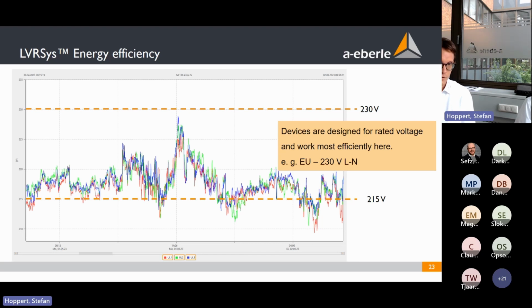For example, all inverter-driven machines are working the best with 230 volts or even a bit higher. Some people in the field say you can save energy if you reduce the voltage. This can happen for some devices. For other devices, it doesn't work or it makes it worse. So we don't want to sell you the system as an energy saving system, but out of our experience, it makes more sense to have it on the nominal voltage, because then all the devices work properly and more efficiently than if the voltage is too low or far too high. With our regulator, we can make it so that you get a stable voltage around 230 volts.